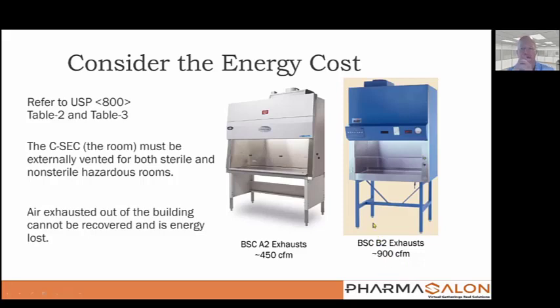So I can tell you that volumetrically, you probably are not handling the amount of chemicals it's going to take to truly be volatile for the people, the process, but I'll let you debate that. But I wanted to bring this to your attention, that every amount of air that is sent out of the building has to be replenished back with conditioned air. If you live somewhere like I do in the South, I don't know if you can tell by the accent, when we're taking that July hot air from outside, and let's say it's coming in at 94 degrees and 70% relative humidity, that makeup air unit has to wring out all of that moisture and condition it to the temperature and humidity, let's call that 64 degrees and 50% relative humidity, to put it into my clean room. And every bit of that is going to get pumped out of the building.